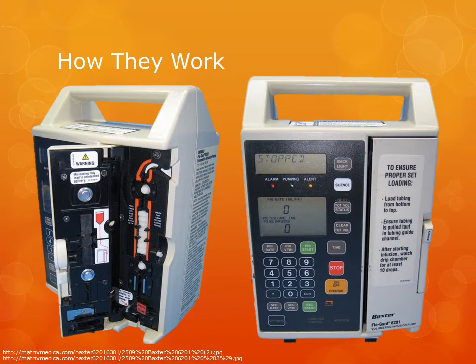So here you can set the rate of infusion and the volume to be infused. Through altering these two amounts, you can set a high amount, low amount, fast rate, low rate, etc., based on what kind of medication you need to put in. For example, if you've got a medication that's very acidic to the body, you don't want to inject this very quickly. Otherwise, you can cause irritation to the veins that it's being inserted into. So, for that, you would put a very low rate but have a high volume so that it would slowly trickle into the body and not cause any irritation.